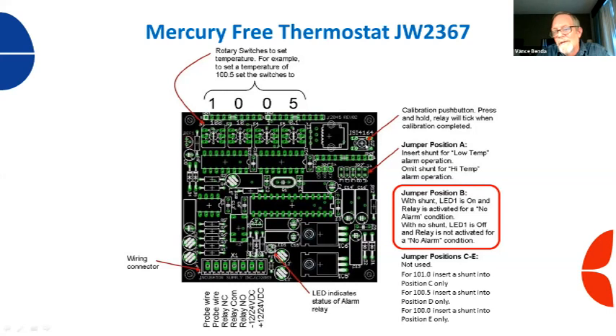Here you have your calibration. We're going to look at an actual picture and we'll go over this. The main thing we wanted to cover on this slide is very important. There are little shunts right here, little jumper pins sticking up. For this system to work as intended, we have to ensure we put a shunt on jumper position B. With that shunt in position B, if this machine is operating at normal temperature, this LED is going to be on. We're connected to normally closed contacts, and this LED says the relay is active. So when the relay is active, this normally closed contact is held open. We're not sending a signal. As soon as this machine goes over the set point, your green LED light would go off and the relay would lose energy and close these contacts, and you're connected normally closed.